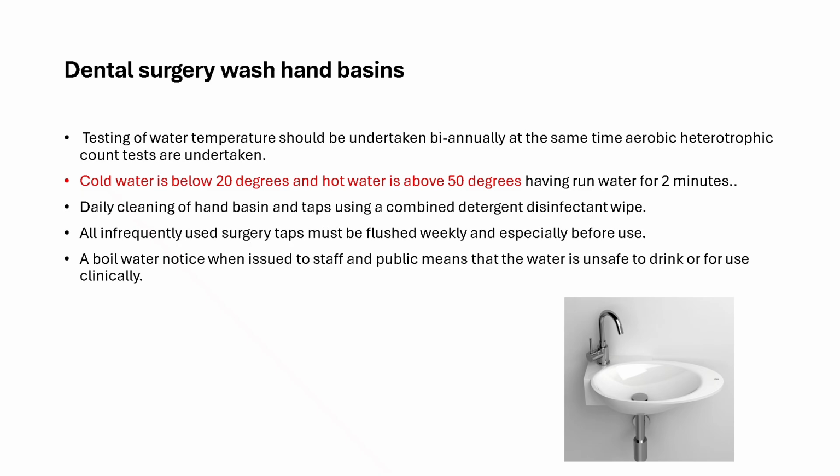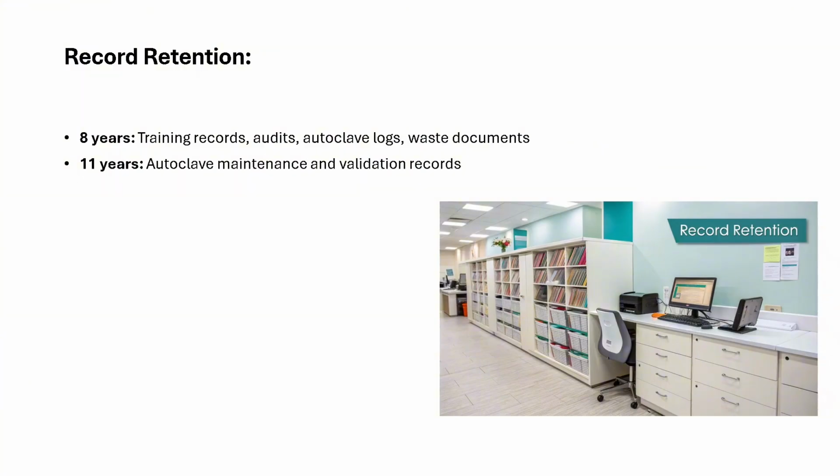All staff training records, auditing, and autoclave logs, as well as waste transfer documents should be kept for 8 years. Autoclave maintenance and validation records should be kept for 11 years.